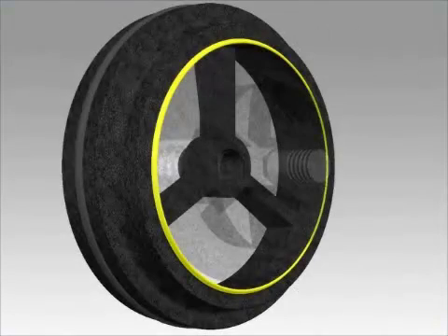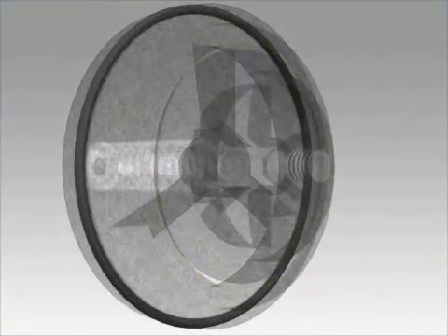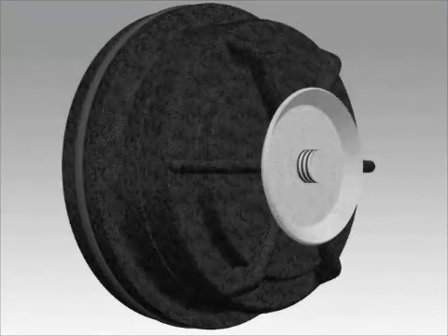Inspect the sharp edge of the seat with your finger for any damage. Inspect the O-ring around the edge of the seat for debris or damage. Replace any damaged parts.